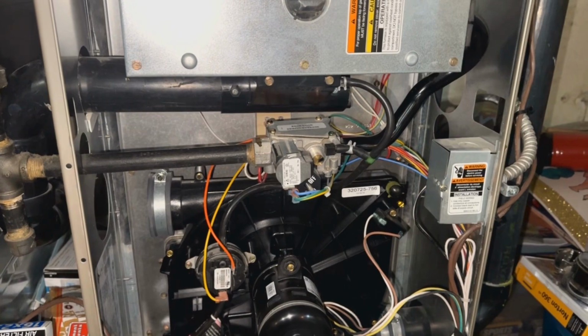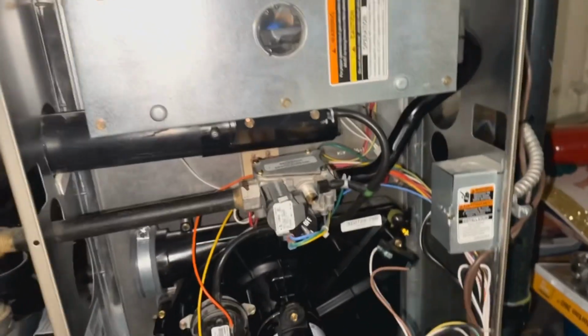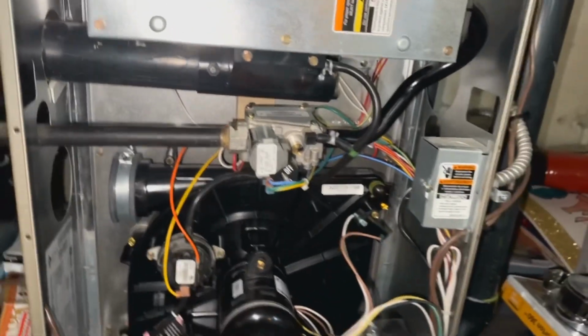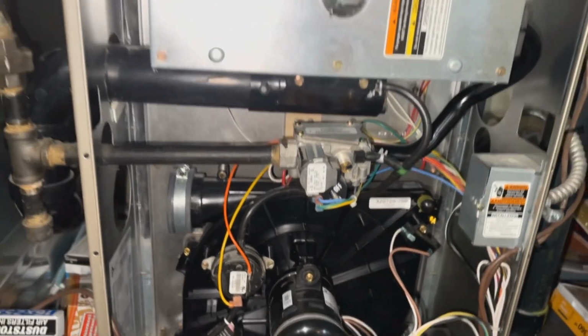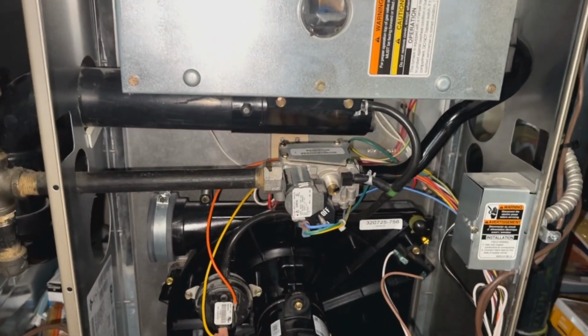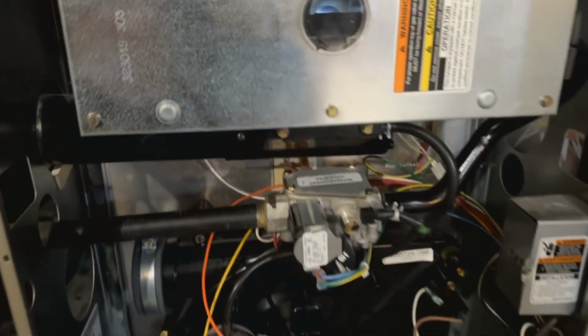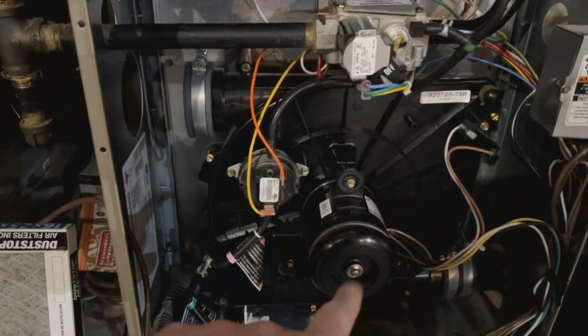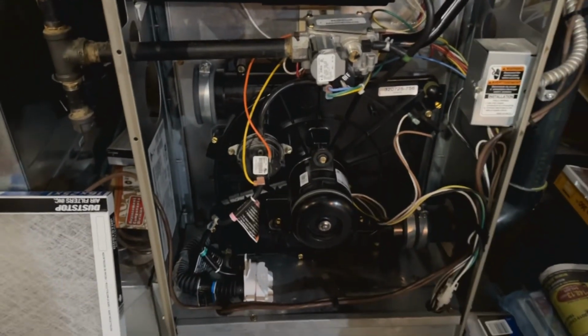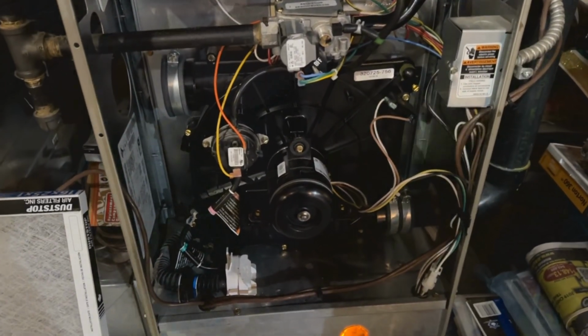Alright, so I just got a call from Paul. He's about 10 minutes out. When you're doing a CO check, the best thing to do is have the furnace run for a bit. So now that Paul's on his way, I've started it up. I've got my motor running, the switch is closed, and right now the flames are blowing blue, which is what they should be. If you get too much orange, it's not a good sign. So I'm going to let this heat up and run, and then we'll get Paul to take a reading.